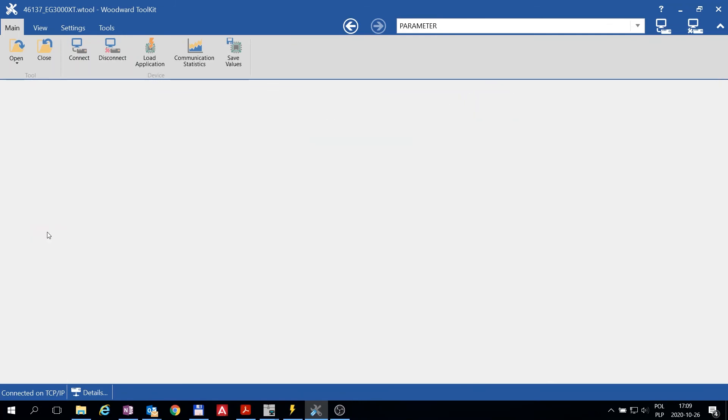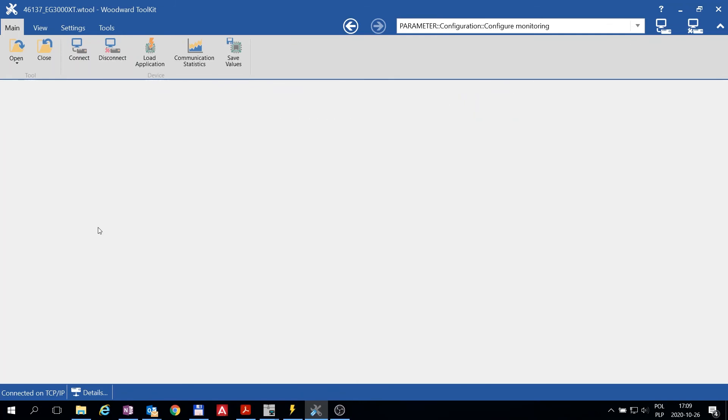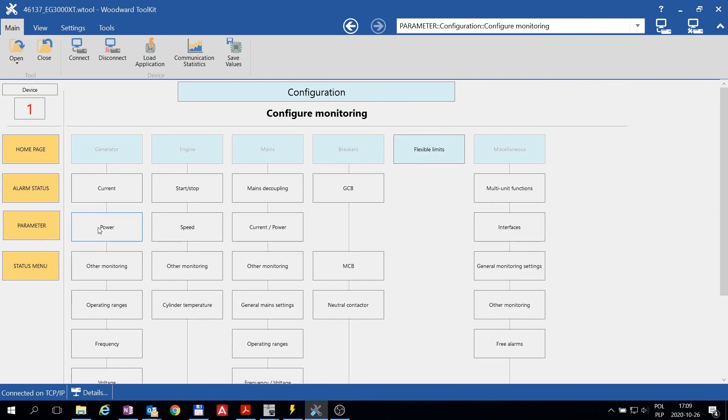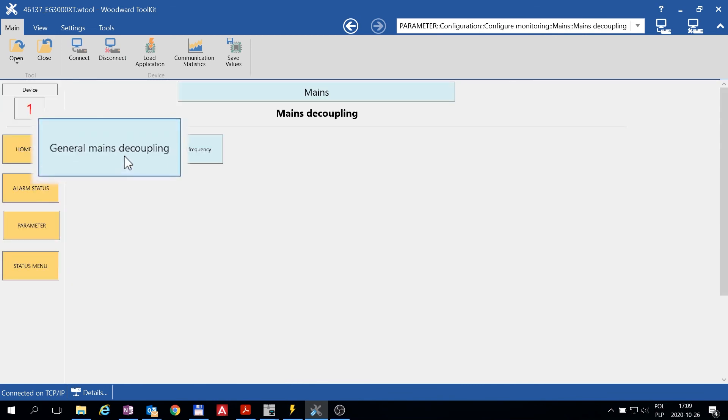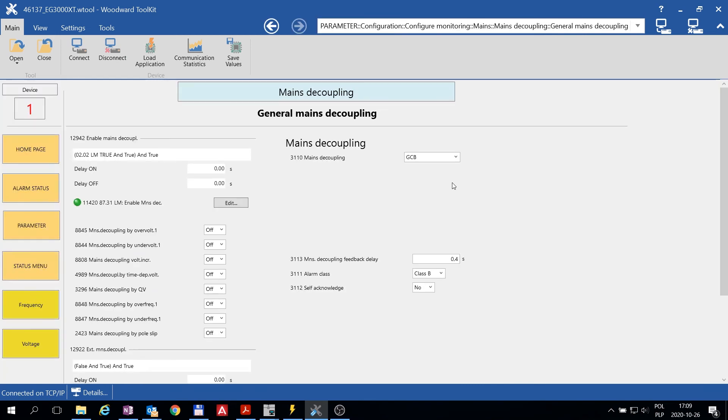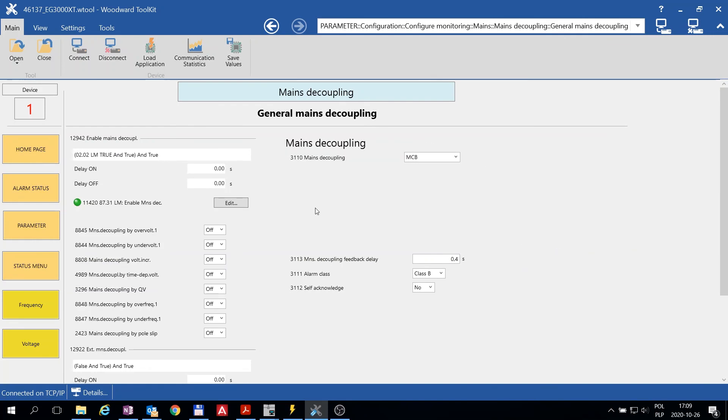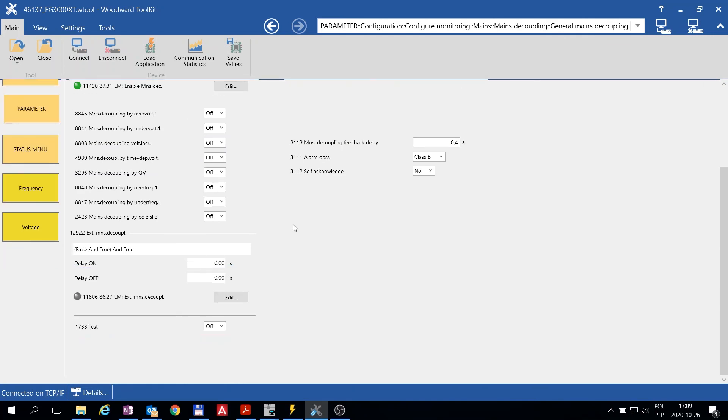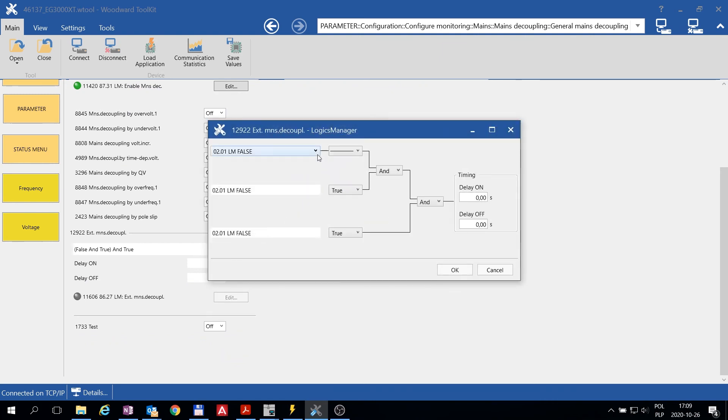If you want to open the main circuit breaker in case of power export situation, this is how you can do it. You need to go to General Mains Decoupling setting and change this parameter to MCB. Then we set up an External Mains Decoupling to activate with our LogicsManager.